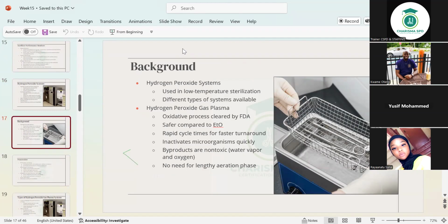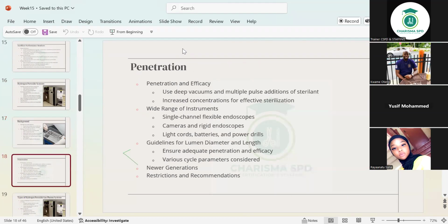It's used in low temperatures. It inactivates microorganisms quickly. Byproducts are non-toxic. No need for lengthy aeration. Okay. Any questions? The penetration, I've told you about it, that the diffusion stage is the penetration. And how effective is it? It's very effective because it uses deep vacuums and multiple pulse additions of sterilant. It increases the concentrations for effective sterilization and has a wide range of instruments: single channel, flexible endoscopes, and cameras, which are some of the heat sensitive devices that we use in this.